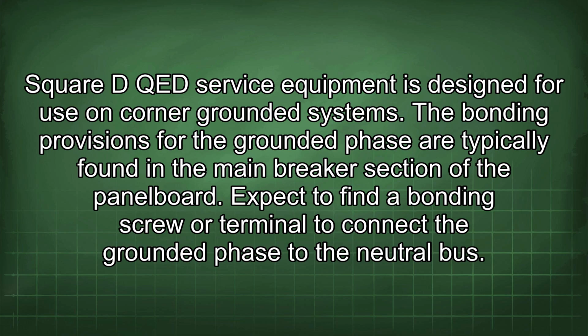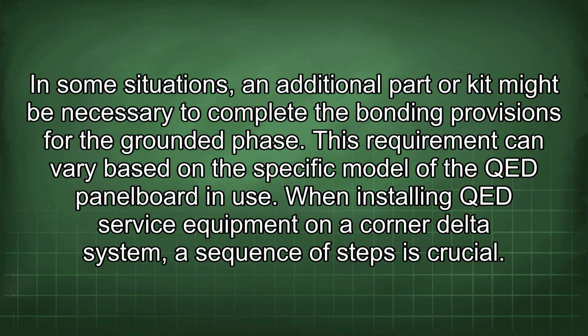The bonding provisions for the grounded phase are typically found in the main breaker section of the panel board. Expect to find a bonding screw or terminal to connect the grounded phase to the neutral bus. In some situations, an additional part or kit might be necessary to complete the bonding provisions for the grounded phase. This requirement can vary based on the specific model of the QED panel board in use.